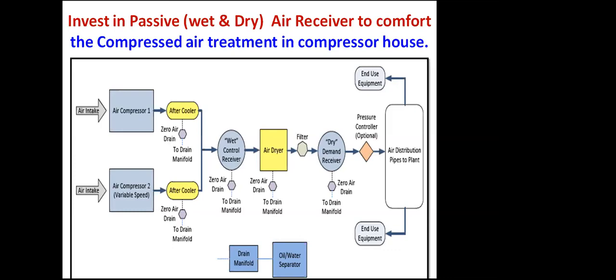Apart from the two receivers in the compressor house, where there is a heavy load and heavy consumption, that also needs a feed receiver or a tail end receiver, as we say. See, invest in passive receivers. It is always good. The compressed air flow velocity is almost 10 meters per second, we say. From the main meter, what is the flow per second and what is it in the branch and sub branches? Each and every line size and each main flow header or branch flow header is different. That has to be worked out to arrive at the optimum meters per second for the compressed air flow. Turbulence in the compressed air is a loss to the compressed air system. Next, please.